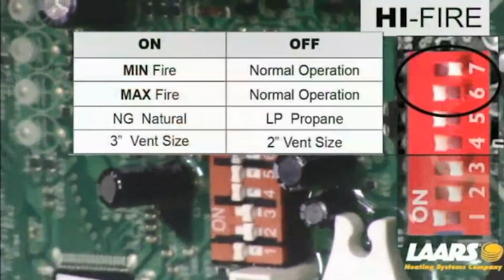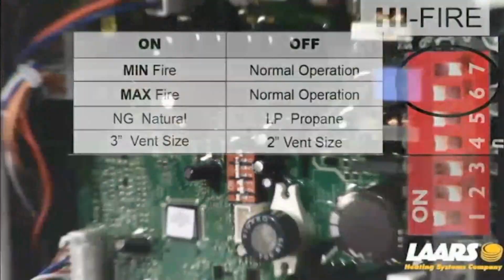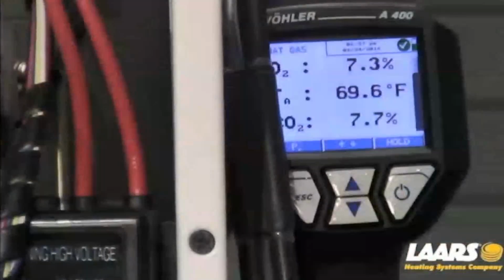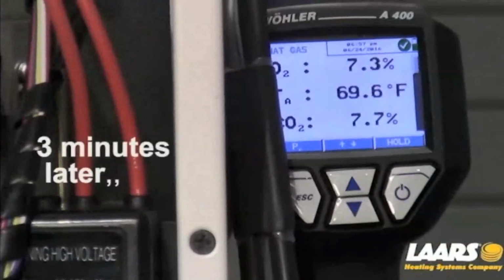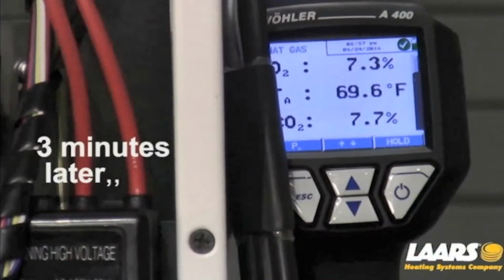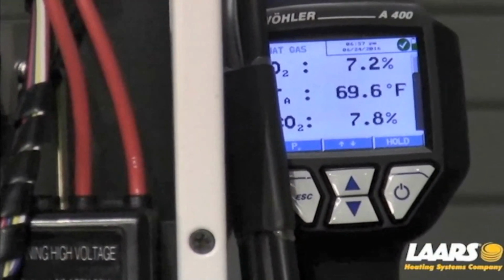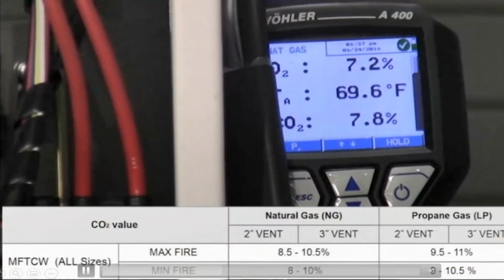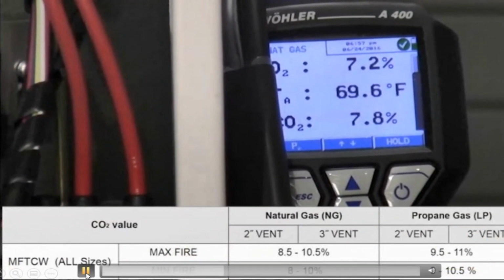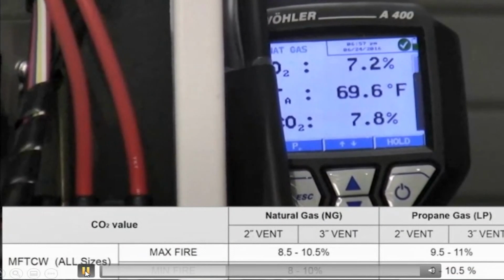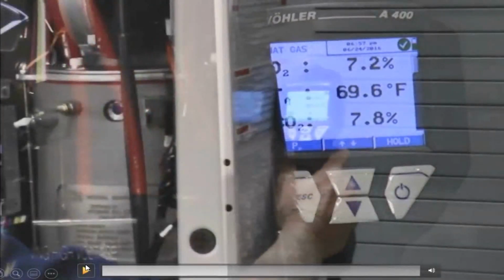Be patient with your analyzers. Some analyzers can take up to 90 seconds to start adjusting. Be very patient with your analyzer. We force the boiler into high fire. So what we're looking for, our range for high fire or maximum fire is 8.5 to 10.5% CO2.